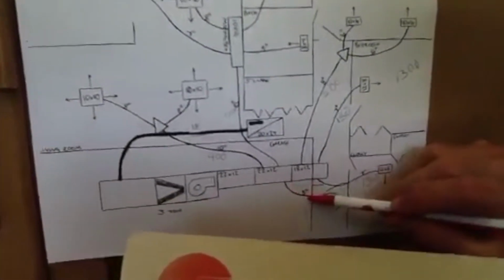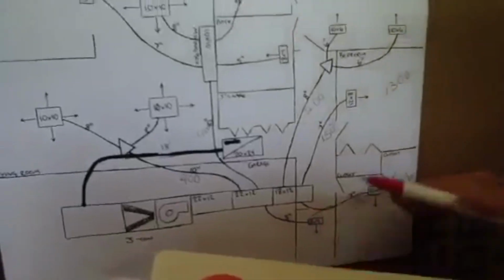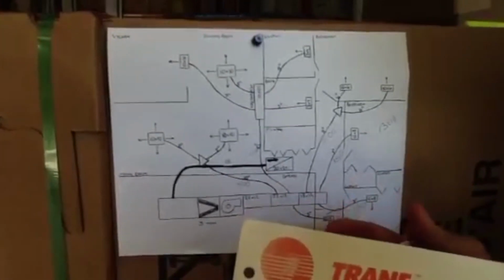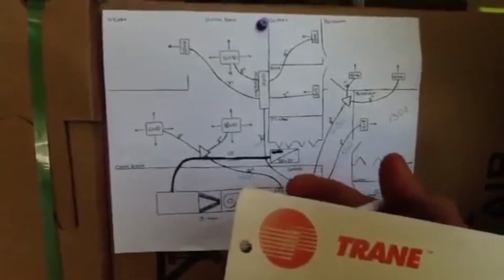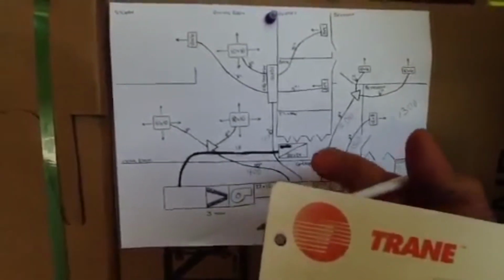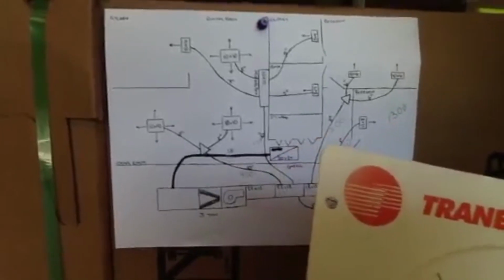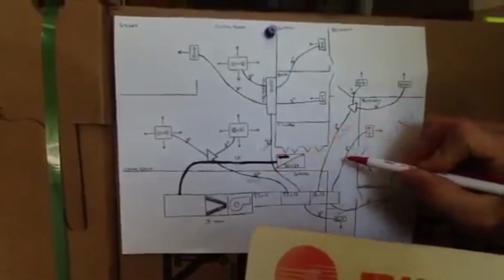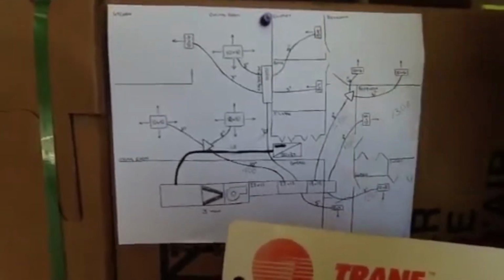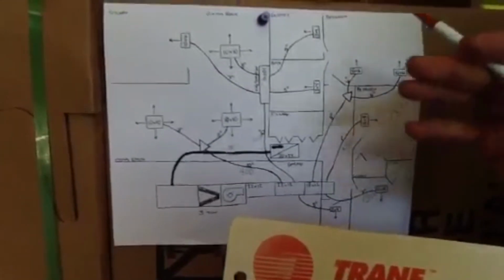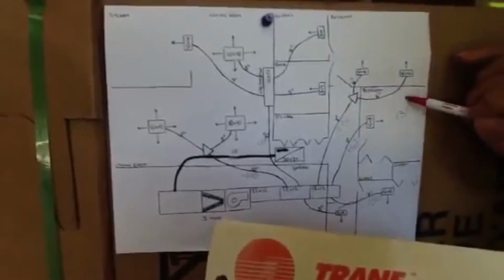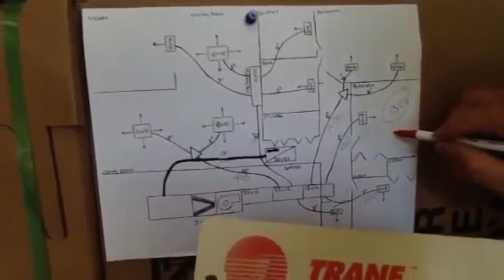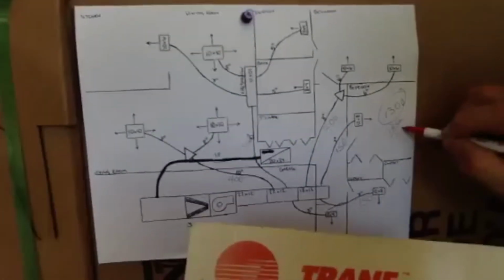Also, you see this little 5-inch flex here? I'm not even going to count that because I know from experience, and my fellow AC people know from experience, if you just give the customer like an extra drop without adding in the airflow for a particular duct system, it won't blow hard and it'll blow nice and quiet. Okay, so right now I've got 1,300 CFMs designed for this particular duct system. I need 1,200. That gives me 100.